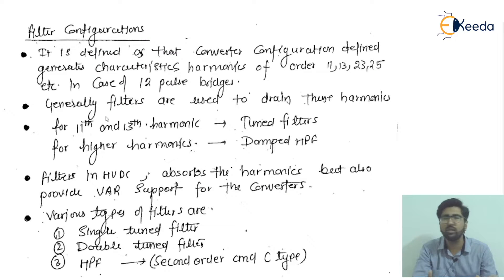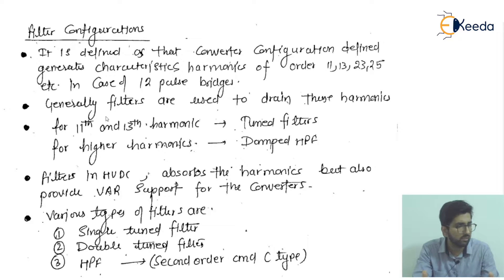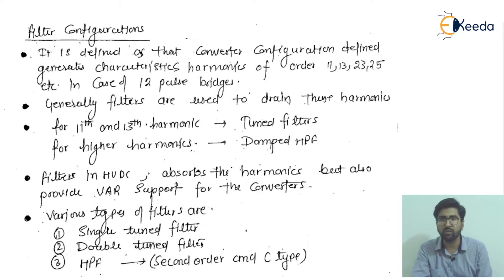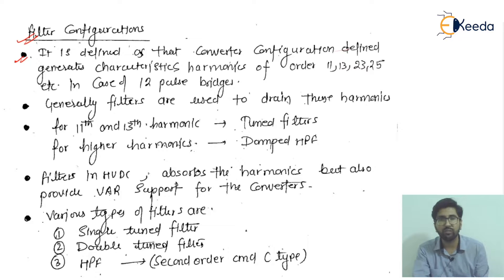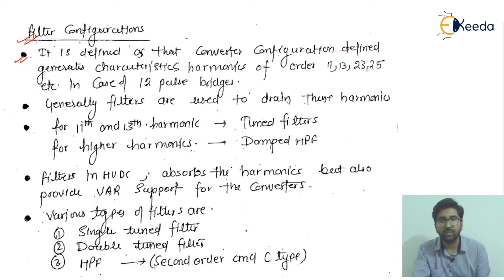What are the different filter configurations used in power systems or system lines for HVDCs? We'll start with HVDC configurations. The converter configuration defines the characteristic harmonics of the order 11, 13, 23, and 25 in the case of 12-pulse bridges, as we have studied in harmonics.